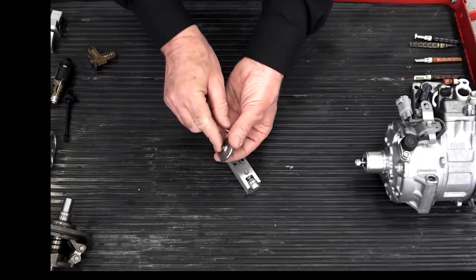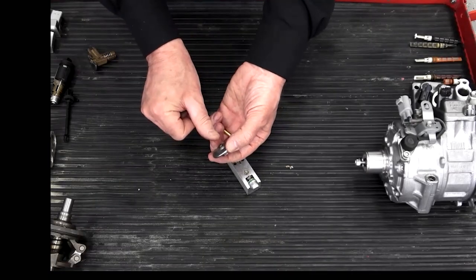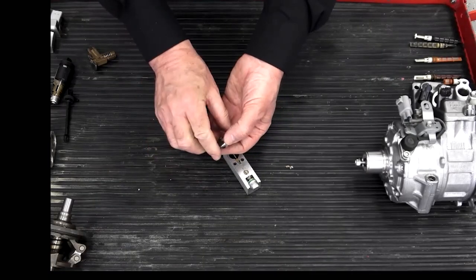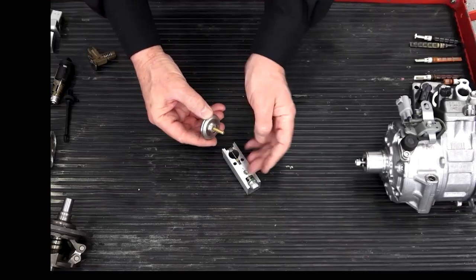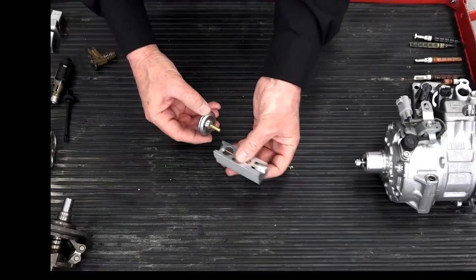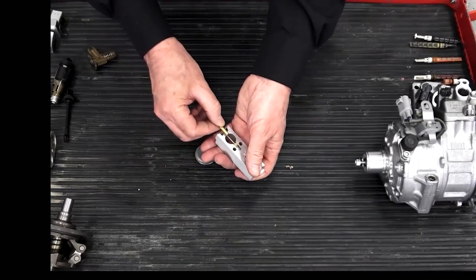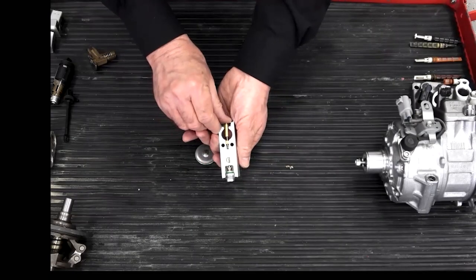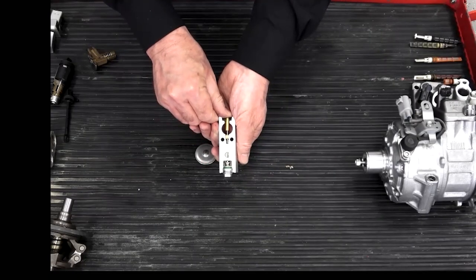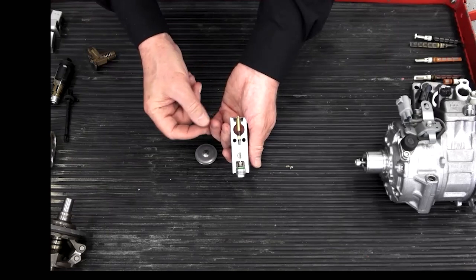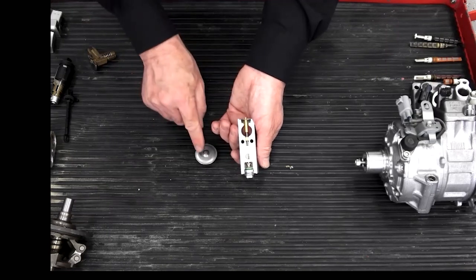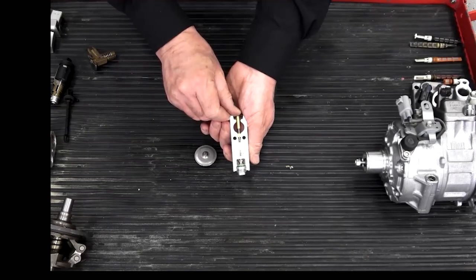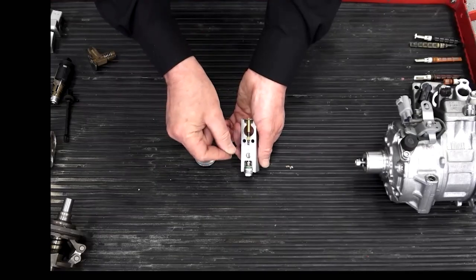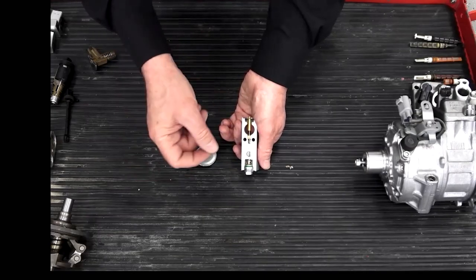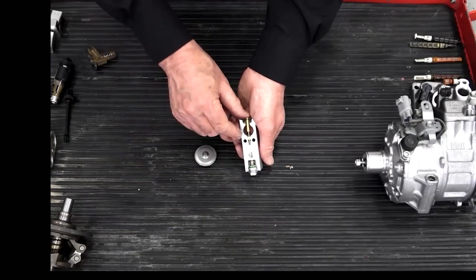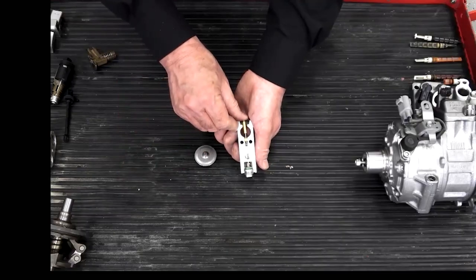So if I heat the refrigerant trapped above the diaphragm, it will expand and deform the center of the diaphragm, which will drive the brass rod down, and so open the ball bearing, open the ball valve wider, right? So you can see that if I increase the temperature here, the refrigerant will expand and drive the rod down. In other words, I can increase the refrigerant flow into the evaporator to match the increasing heat load, and of course, vice versa if I turn the blower back to low speed.